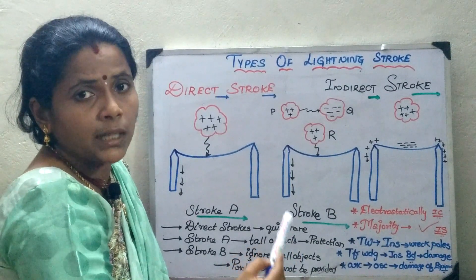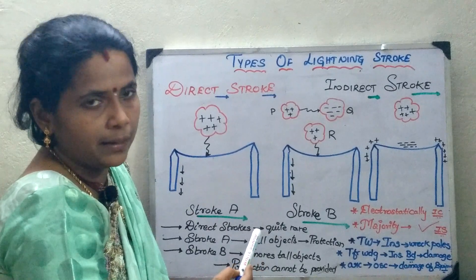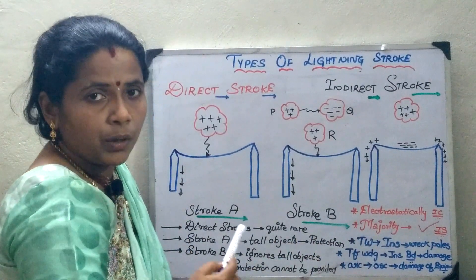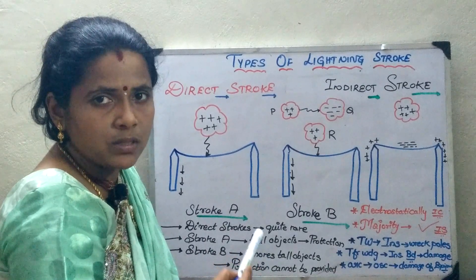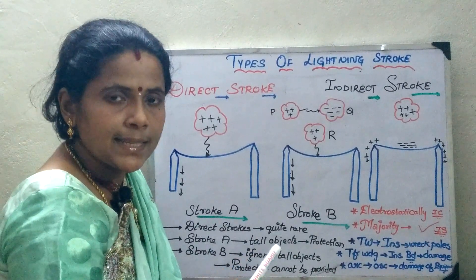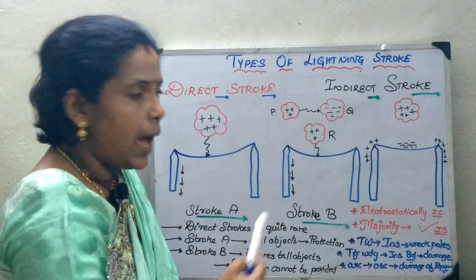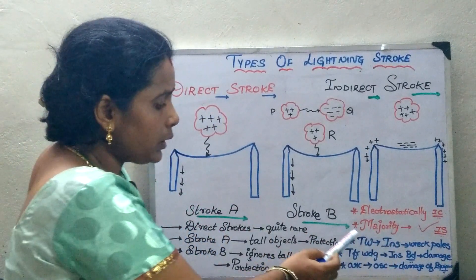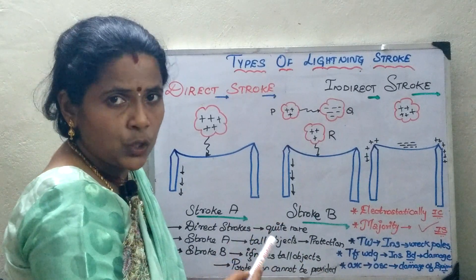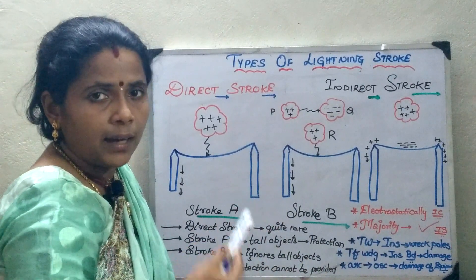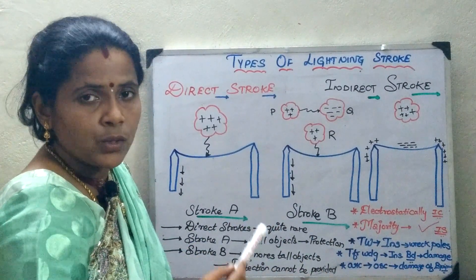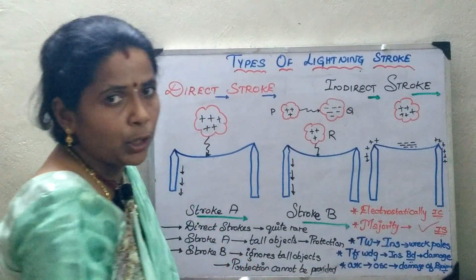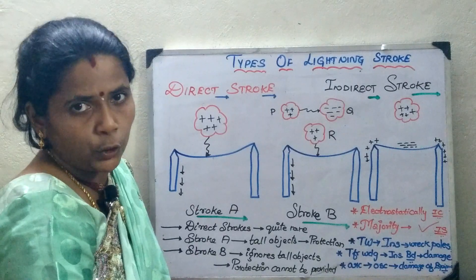The harmful effects of lightning are as follows. First, it creates travelling waves; if these persist for a long period, they result in insulation breakdown and also wreck the poles. Second, if lightning affects the transformer winding, it immediately leads to insulation breakdown and damage of that equipment.